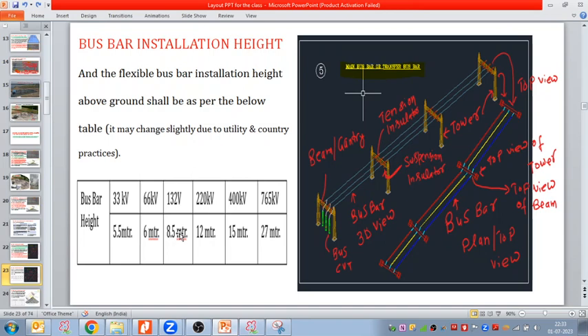Usually, in India, for 33 kV we plan 5.5 meters above ground. For 66 kV we plan 6 meters above ground. For 132 kV, 8.5 meters above ground. For 220 kV, 12 meters above ground. If I take this ground level, then 12 meters above the ground. For 400 kV, 15 meters above ground. For 765 kV, 27 meters above ground. This is how we do the stringing for the main bus bars.